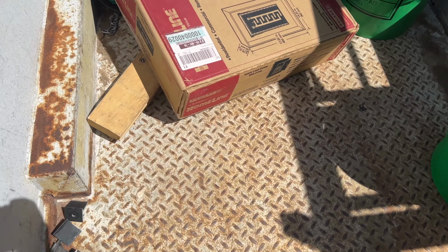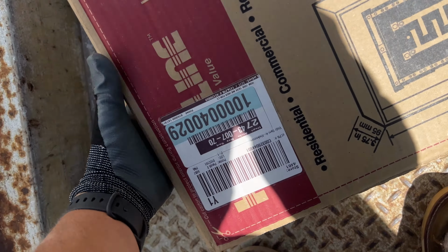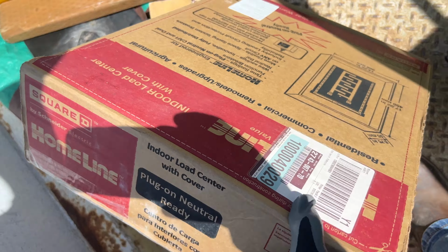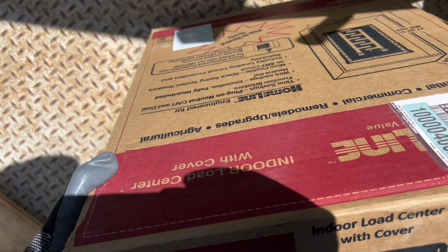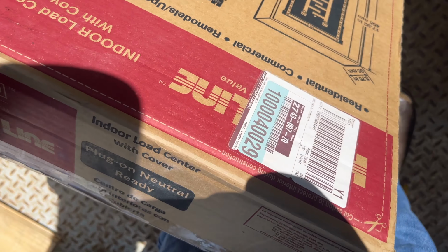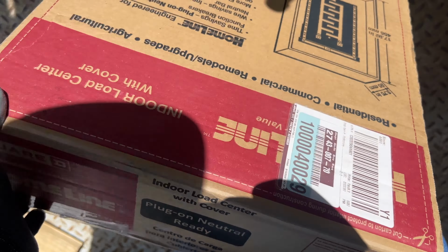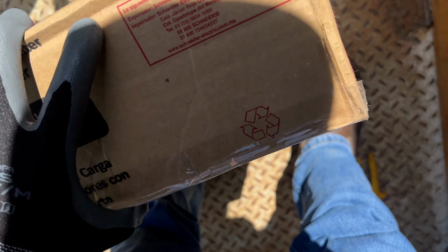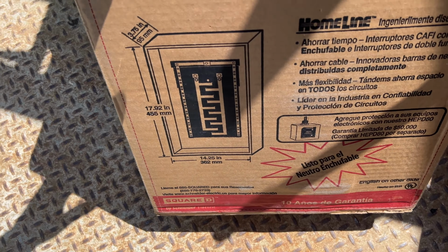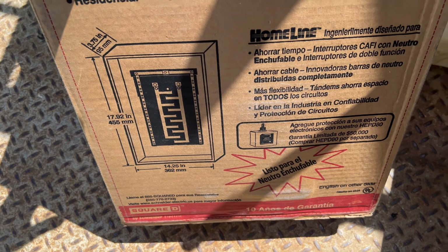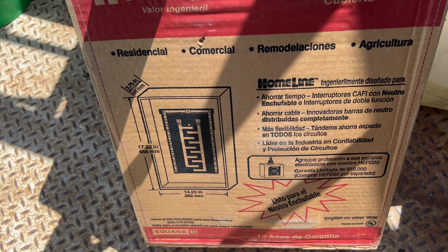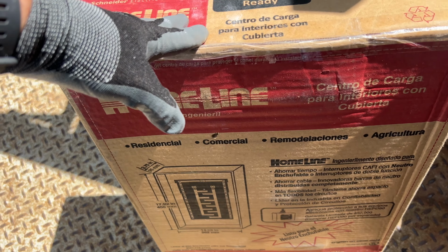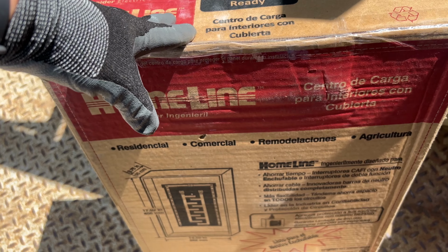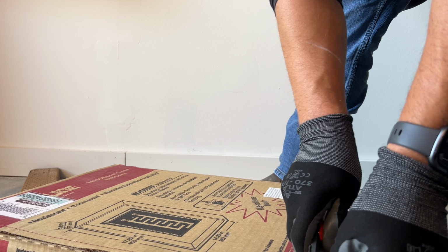I like getting all my boxes hung, and the last thing I needed to do was hang a panel. So I have this one from Square D. This is a surface mount or flush mount panel, and I like that it had a main breaker on it, and you could change that breaker for whatever you needed, however you're designing the system. I'm gonna get this mounted up so that I have all of my boxes mounted before I start running my raceways.